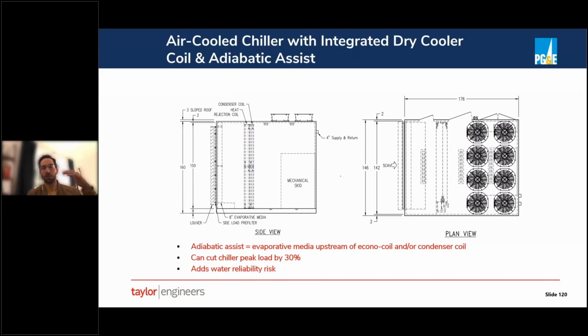And by doing so, you're reducing the lift across the chiller, and that increases chiller efficiency, which in turn reduces electrical load. So it allows your electrical engineer to potentially size systems more aggressively than they would have with just a standard air-cooled chiller. In this example, we've sized these systems and seen a 30% reduction in peak electrical load. The downside of this sort of system is that it obviously adds a lot more complexity, because now we have makeup water that we need to provide to all of the adiabatic cooling pads that we wouldn't have had otherwise. And we are also adding a reliability risk, because now the system relies on water under design conditions to make sure that the chillers can provide their design capacity.